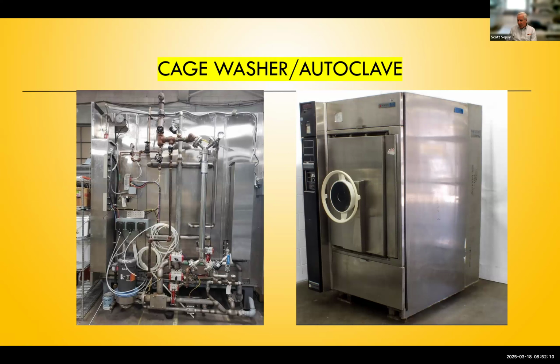And again, you could buy onboard steam generation for autoclaves and perhaps modify cage washer operations. They have intermittent and dynamic steam demands, but the heating requirements could be reduced by lowering the temperatures and could be eliminated completely by electrically boosted high temperature hot water. Maybe you preheat with a heat pump and finish it off with electric resistance heat. What they really need is 180-degree plus water for the sterilization.